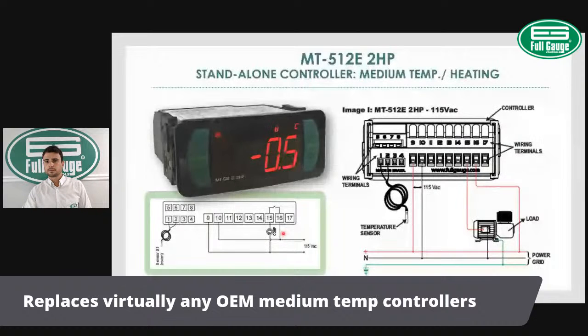So let's go on in here. What I was talking about was the independent relay circuit. That's what we have in here. One of the good things about having an independent relay circuit is that it allows me to power the controller in 110 and run a 230 compressor through it. Or, for instance, run a 12 volt solenoid valve, powering the controller in 110.